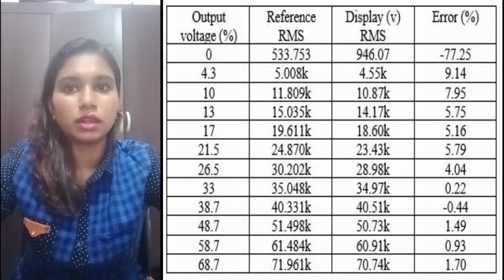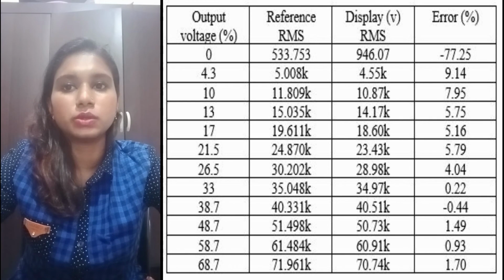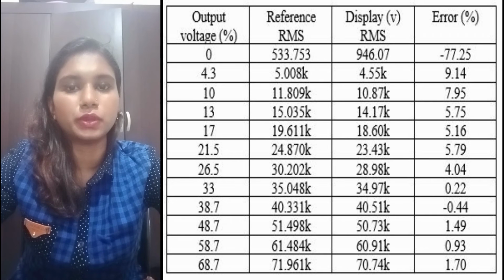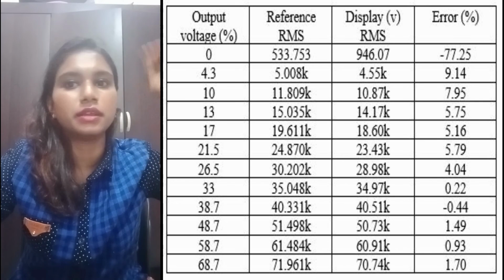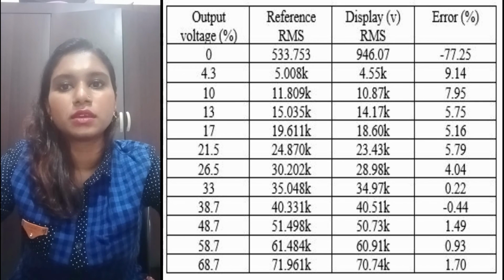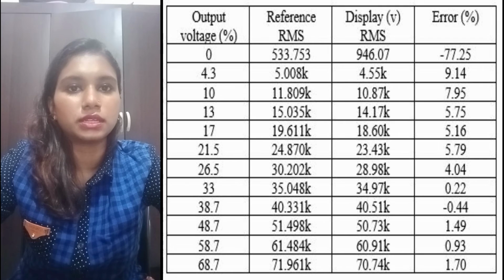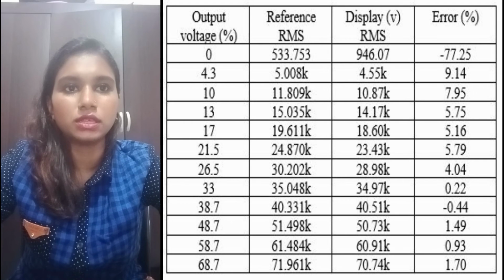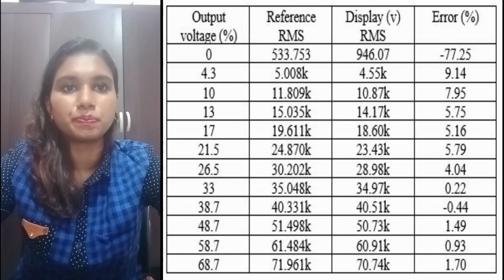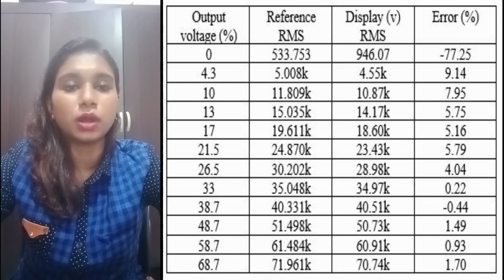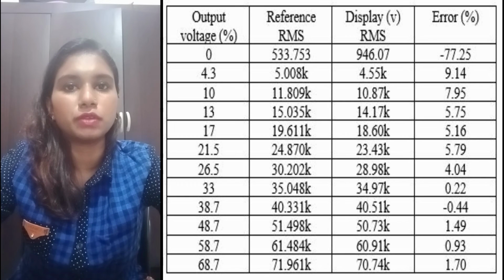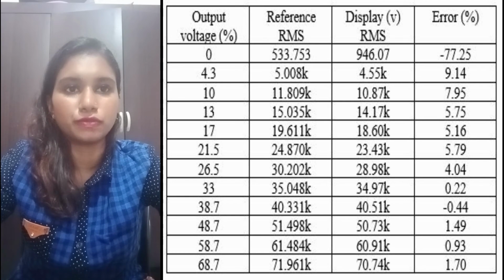5.16%. Okay, now when the output voltage is 26.5%, the reference RMS is 30.20 kV and the display value is 28.98 kV and the percentage error is 4.04%. When the output voltage is 33%, the reference RMS is 35.048 kV, the display value is 34.97 kV, while the percentage error is 0.22%. When the output voltage is 38.7%, the reference RMS is 40.331 kV, the display value is 40.51 kV, while the percentage error is negative 0.44.